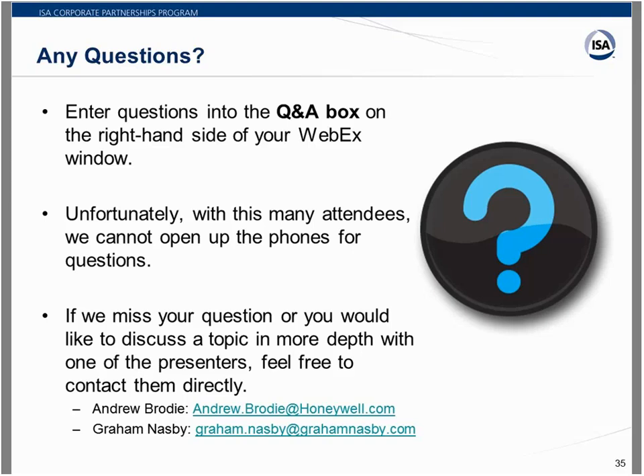However, one of the caveats is in some networks, you'll use things such as network address translation or routing rules, where there may be additional routing steps that the control system will navigate to get to a device. The device will have an IP address, but it may not be a public IP address. It may be part of a private network or a routed network for security reasons, and that's something you'll address when you do the design of these systems.